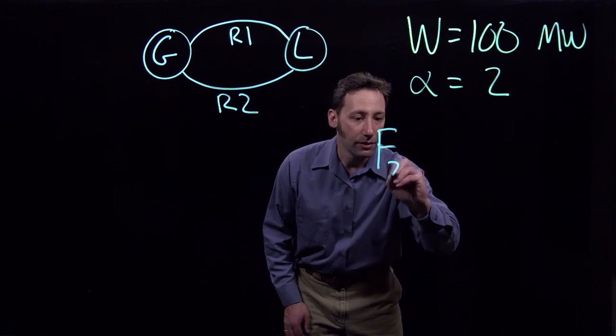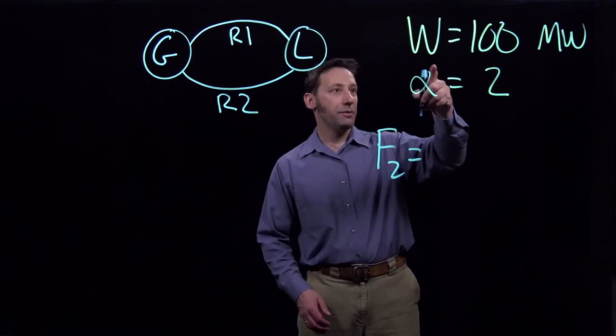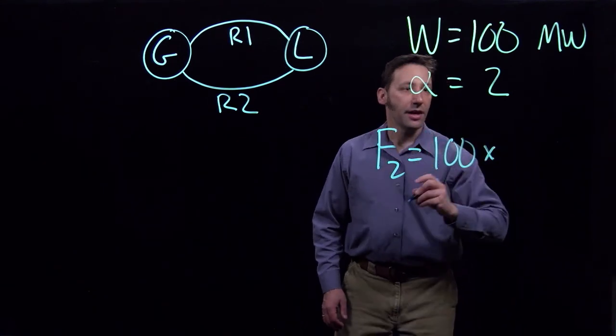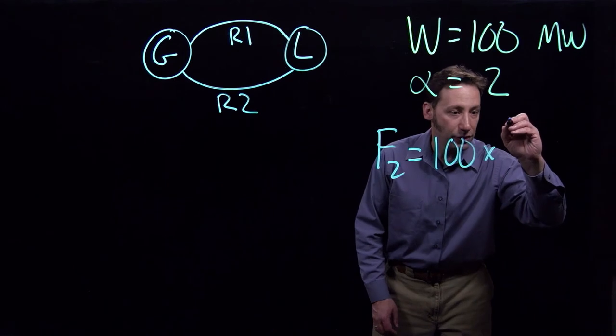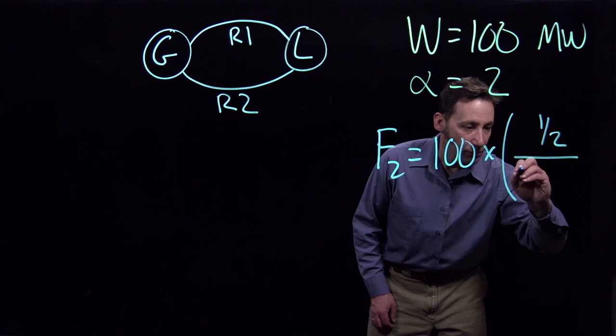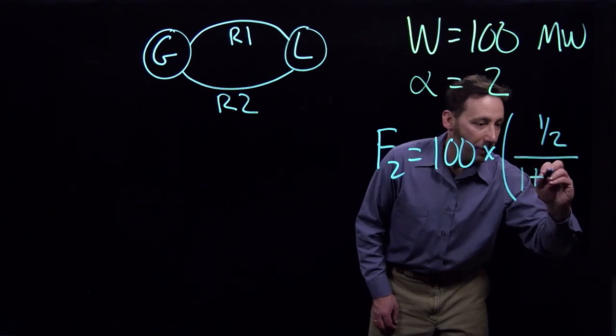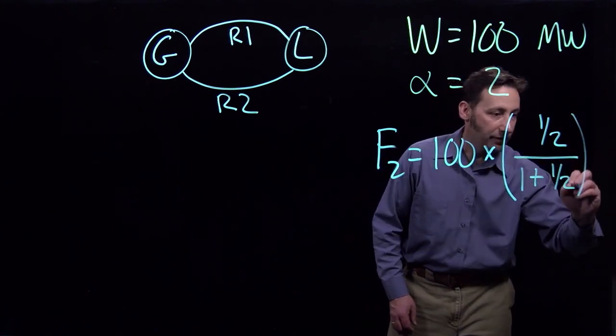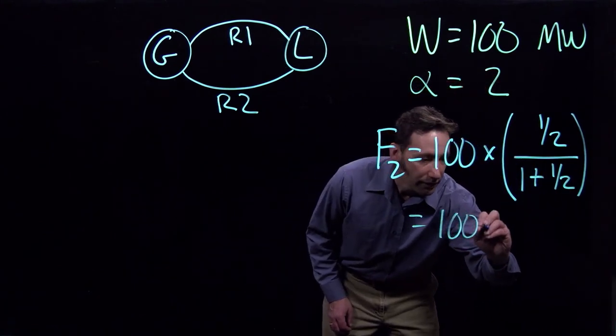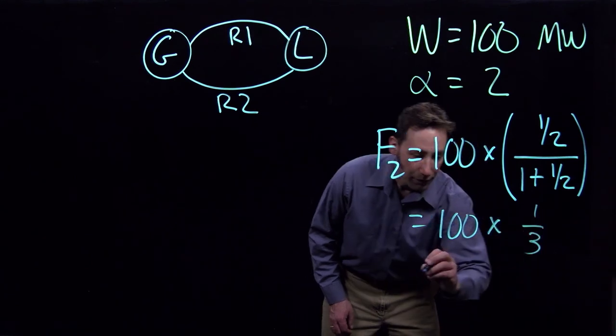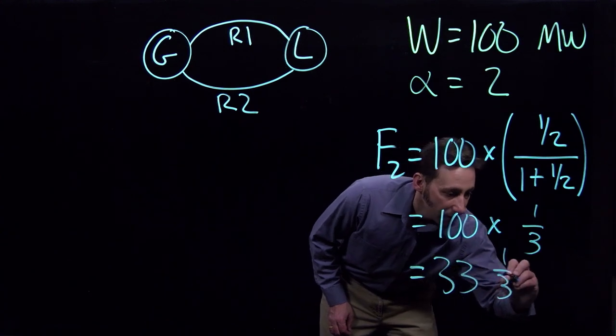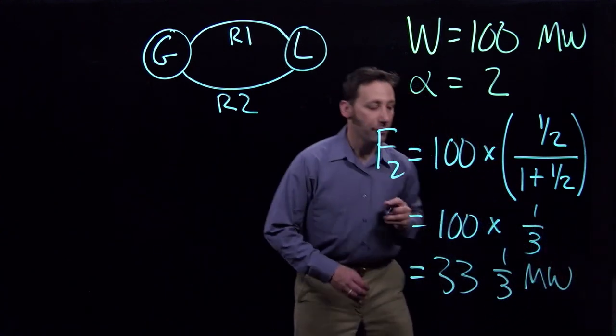For the flow on line two, that's going to be equal to w, or 100, times the distribution factor for line two, which is one half divided by one plus one half. So this is going to be equal to 100 times one-third, which is 33 and one-third megawatts.